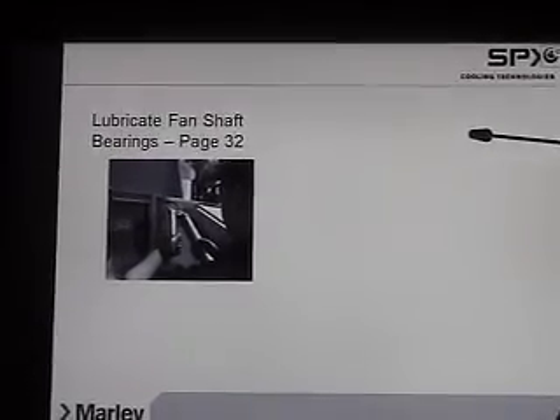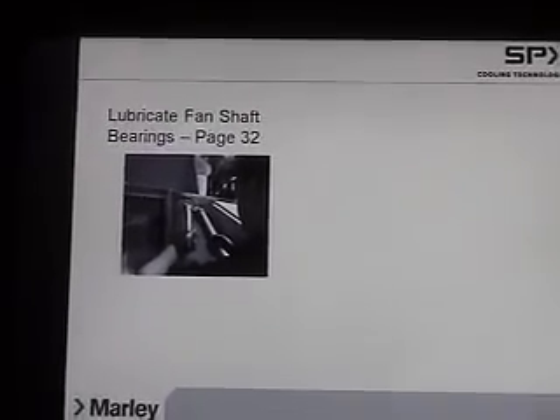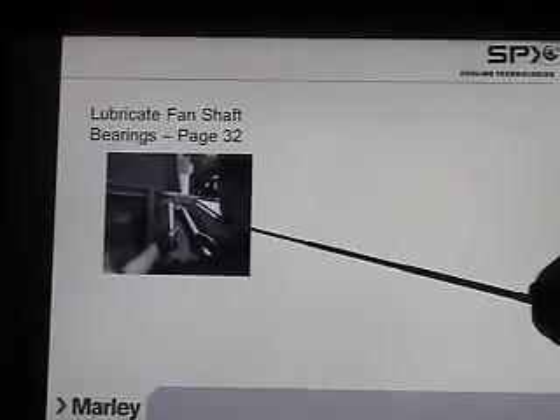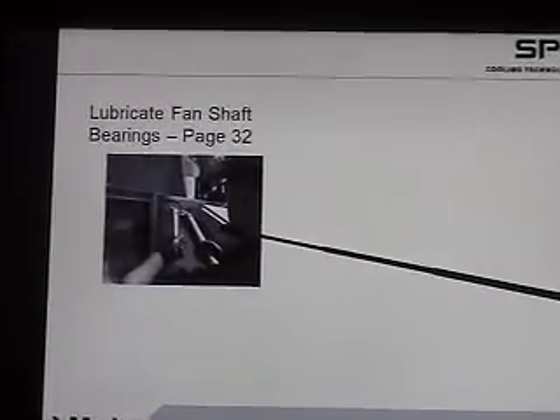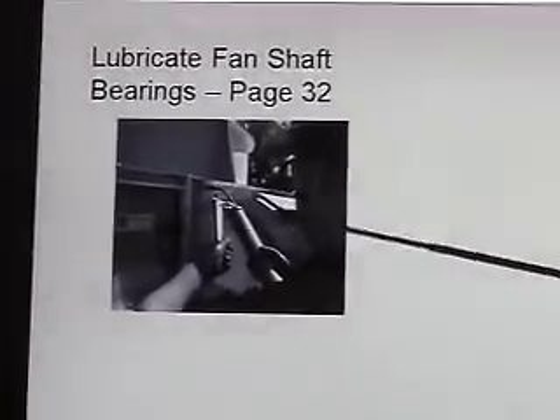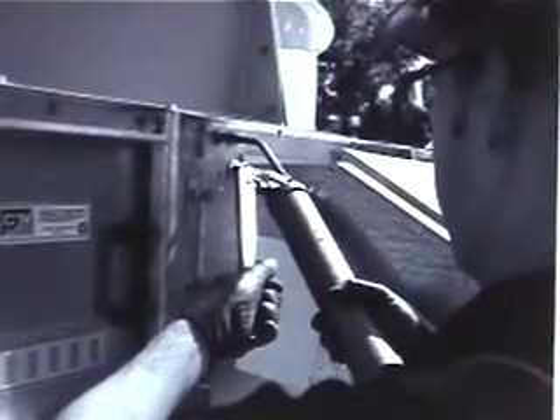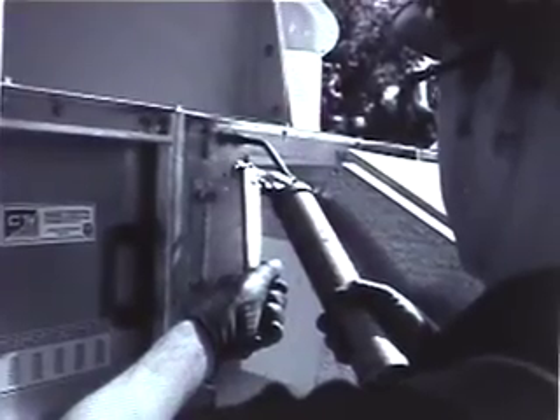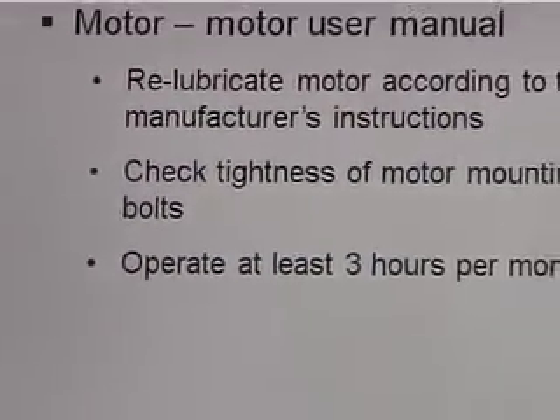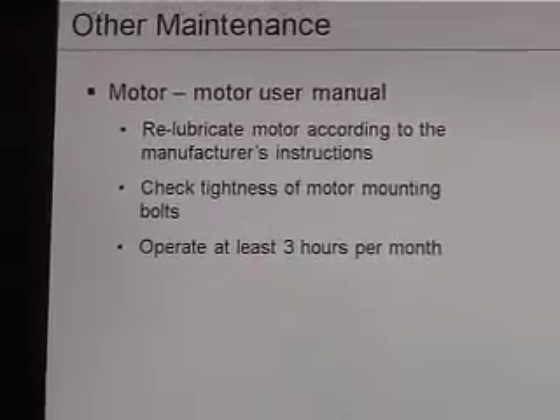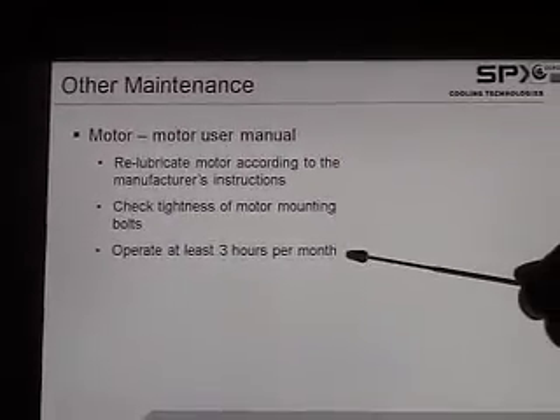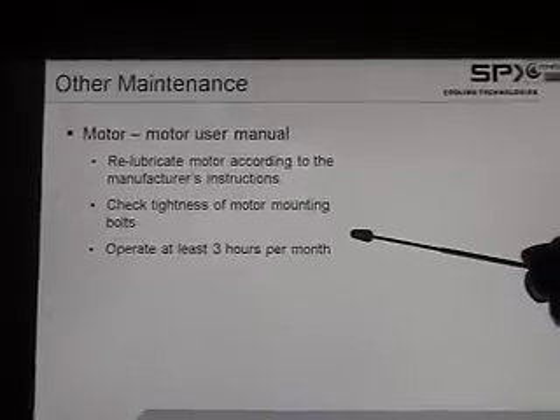Lubricate your fan shaft bearings, and that's on page 32. It's right here next to where the motor's mounted. This is the safety cover for the motor. And there's a motor user manual also. And remember to run your cooling tower at least 3 hours a month.